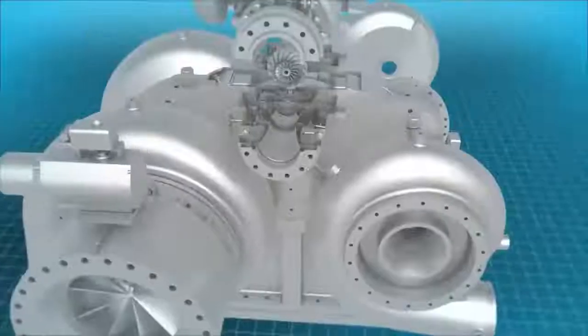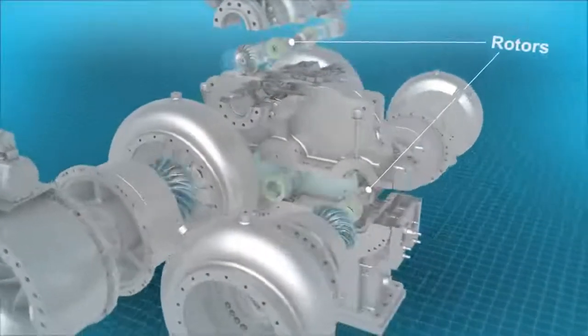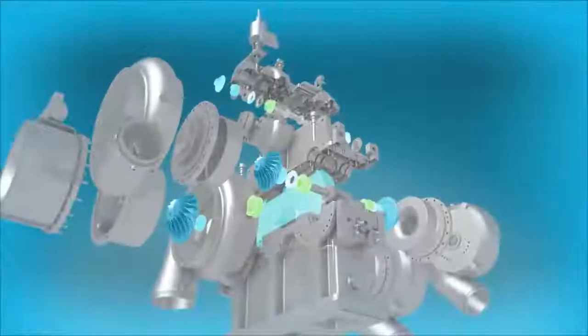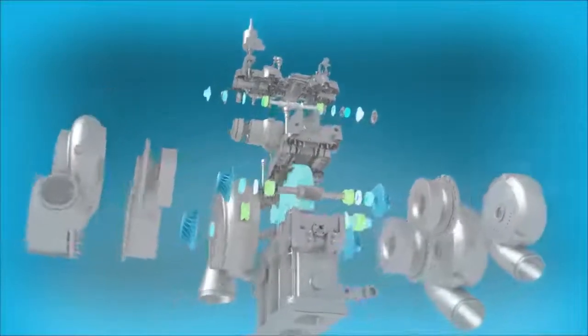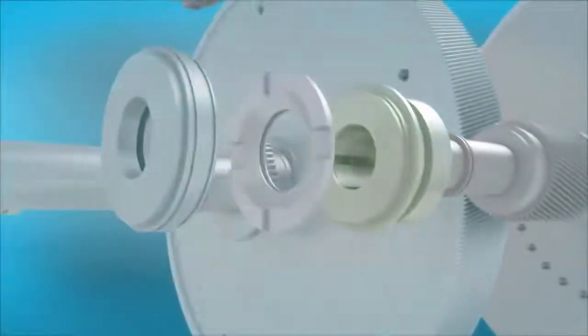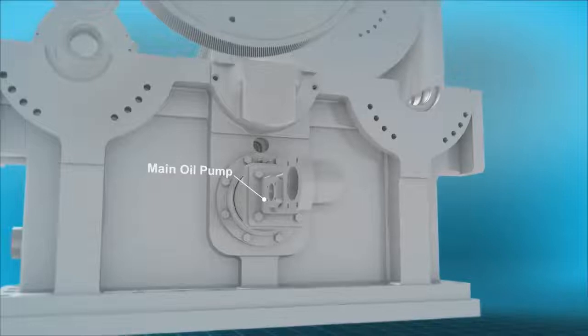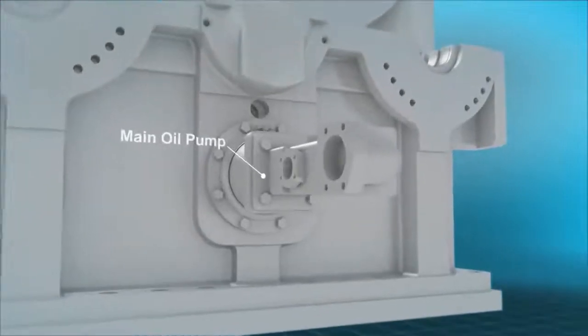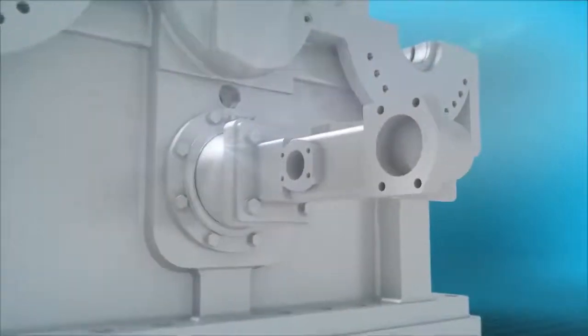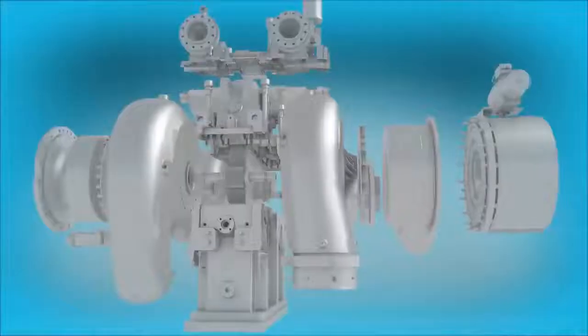Integrally Geared Compressors deliver multiple speed capability by placing rotors on separate pinions. Each compression stage runs at the optimum speed for high efficiency. Compressor bearings and gears are lubricated by the main lube oil pump, which is driven through the bull gear for reliable oil flow.